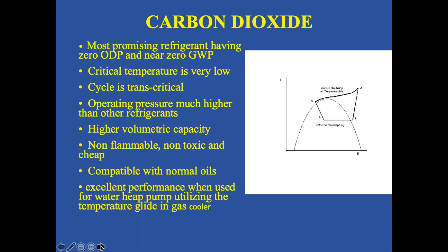So in India, you cannot condense carbon dioxide in a single stage operation, because our condensing temperatures will always be higher than 31 degrees centigrade. Operating pressures are much higher. The operating pressures of carbon dioxide are 60 to 70 kg per centimeter square. So all our equipment, which currently uses 15, 16 kg, has to be developed and designed to use this refrigerant. High, but it has advantages: high volumetric efficiency, non-flammable, non-toxic, compatible with normal oils, and excellent performance for heat pump duty. These are all the advantages of carbon dioxide.